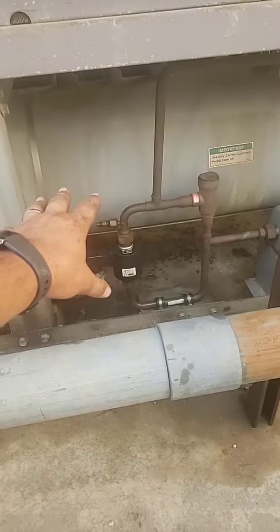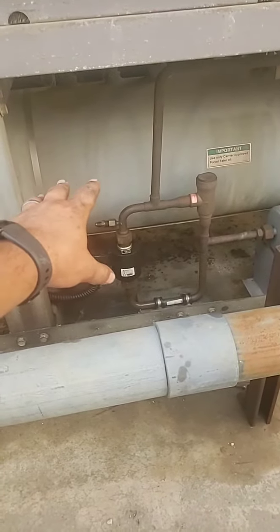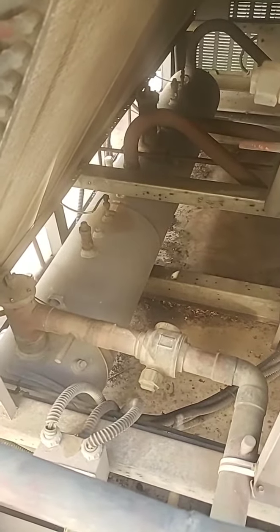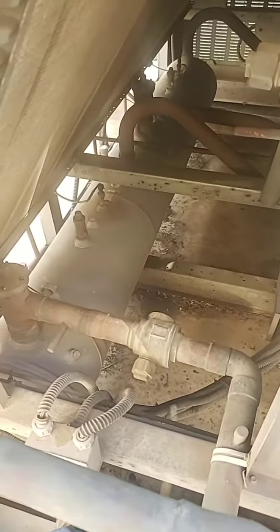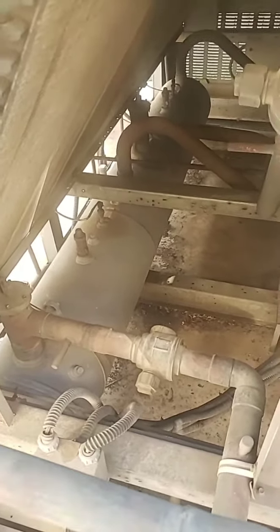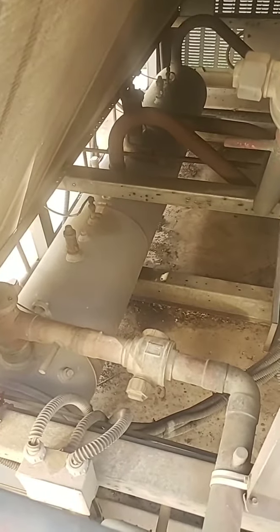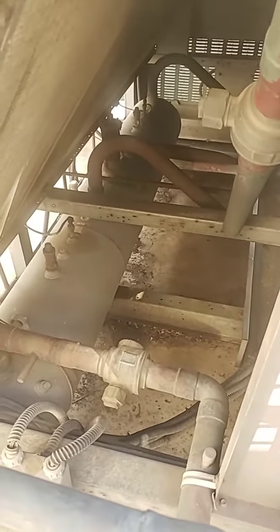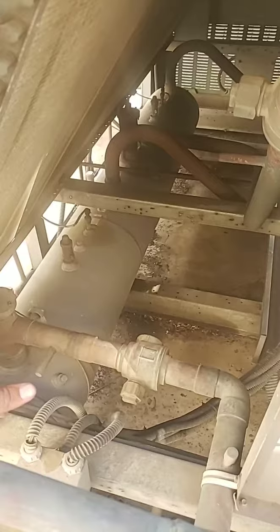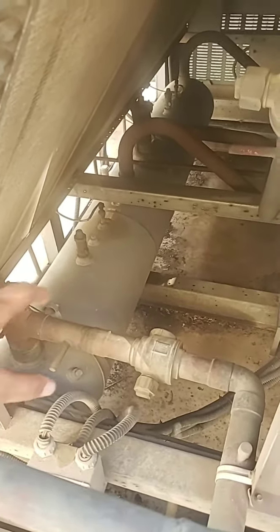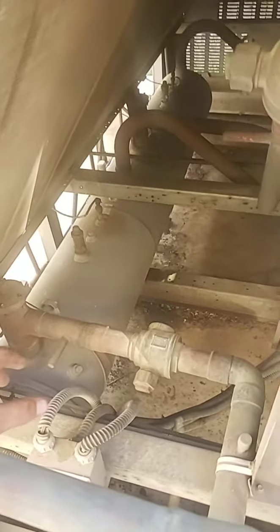You gain a lot of efficiency, for one, not running as much oil through your condenser, because you don't lose as much. I'm going to step back around here. You don't lose as much efficiency because your oil can actually create a barrier inside your condenser and make it harder for the condenser to properly process the BTUs. So the less oil you can put through your condenser coil, the better. The other thing is we've got to make sure that we're keeping enough oil in the system that we can actually pump it back into the compressor to properly lubricate our bearings. So that's why it's very critical that this oil separator function properly.